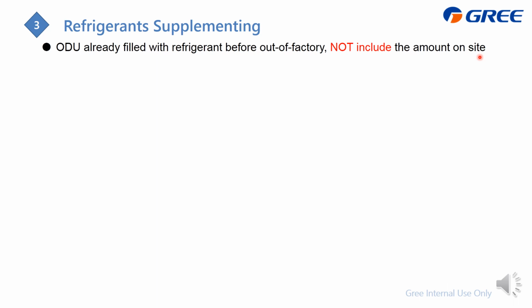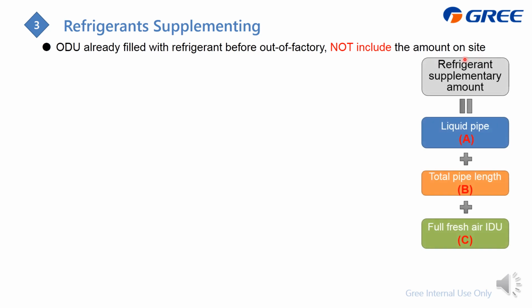How to calculate it: I divide it into three parts. This is the total additional amount, and I divide it into A, B, C. A is for the liquid pipe, B is for the total piping length, and C is if you connect with the fresh air indoor unit, you also need to add some more refrigerant. And here is the detail.